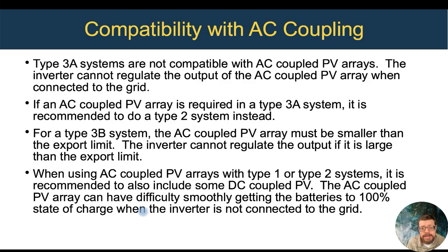Now, the ones that interact with the grid, the type 3 and 4 systems, those will also dark start from the grid if you've had a low battery shutdown. So that's less of a concern there to have some DC coupled PV, because you can rely on the grid a little bit more to handle that balancing, always absorbing the extra from the AC coupled PV array. But when you are off grid or just using the grid as a generator type backup, you really have to think more about how can I recover myself from a low battery situation and not need that grid coming in, and get back to where my AC coupled PV array works. And that's where having at least some DC coupled PV array is a good design.